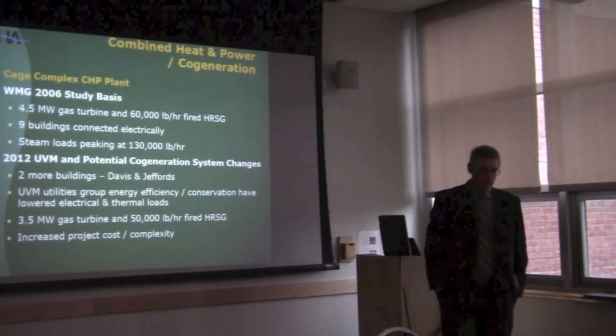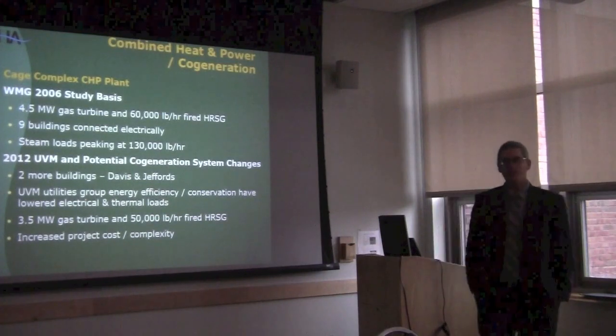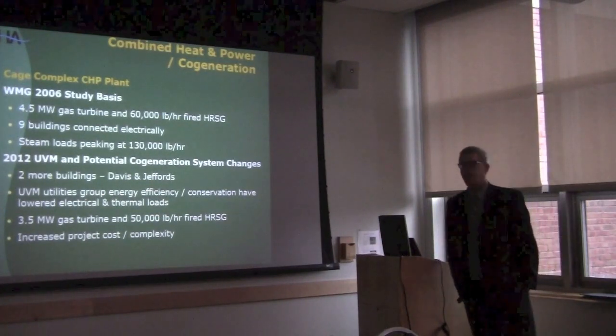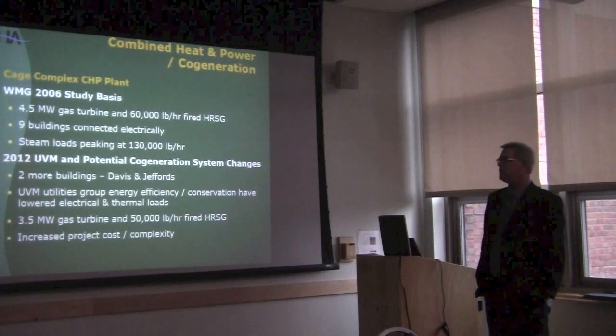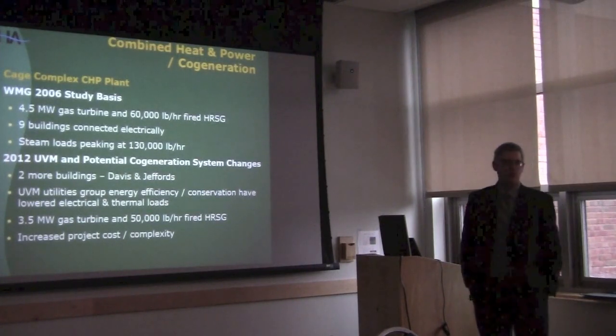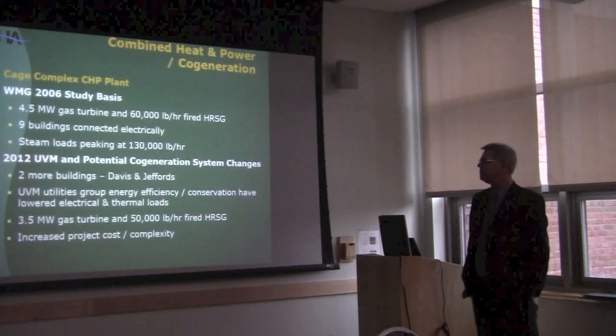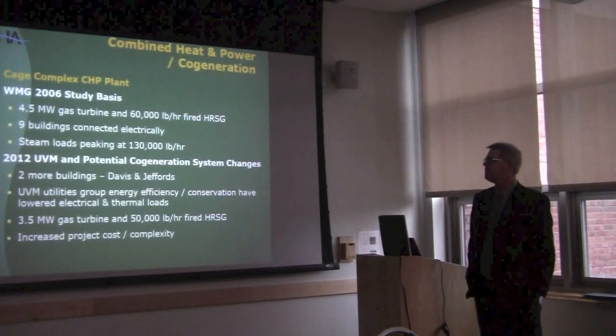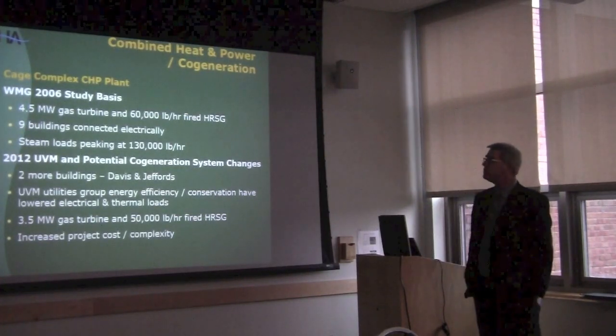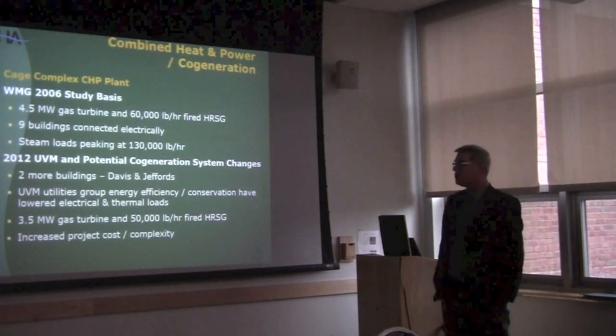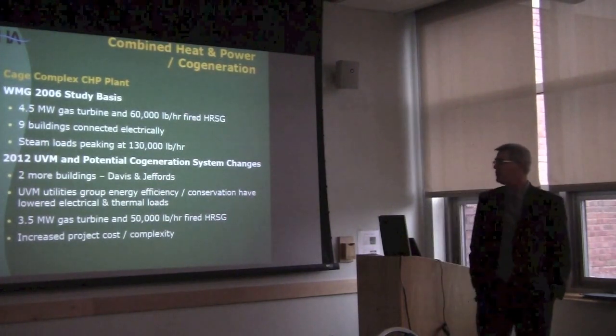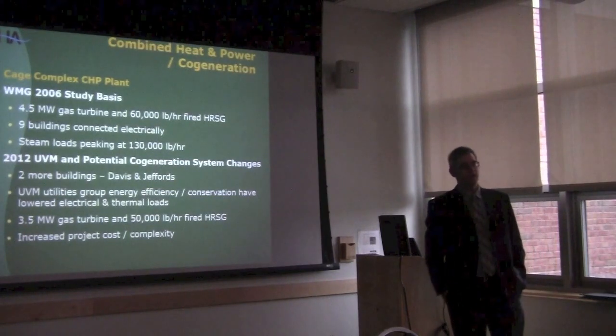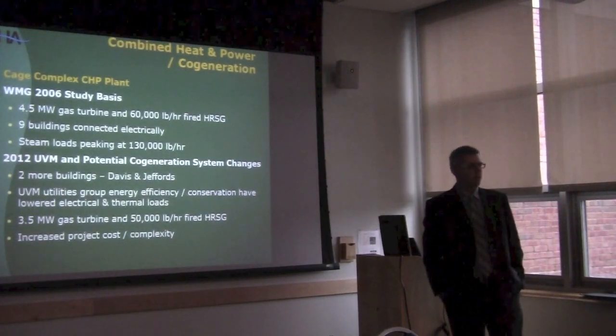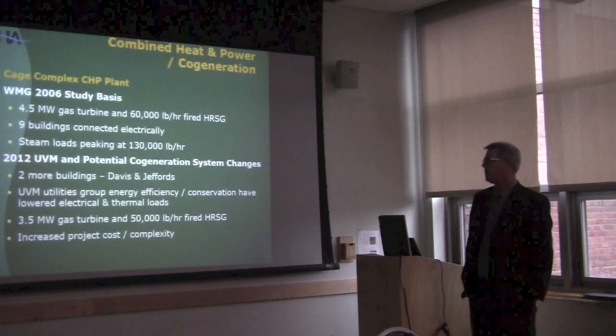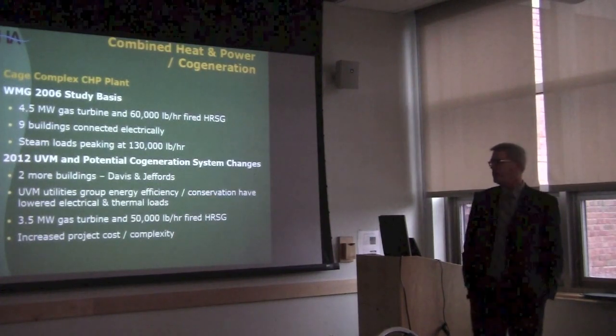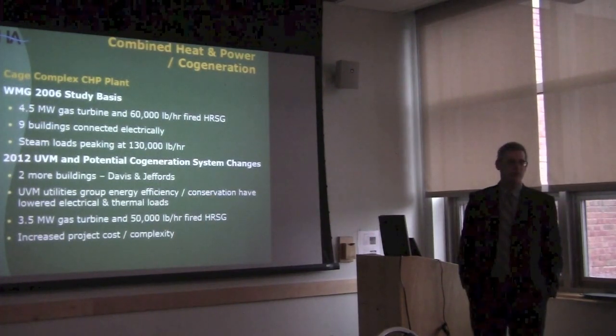At that time, steam loads out of the cage were peaking at 130,000 pounds per hour or higher. In 2012, based on information from physical facilities staff, we've added 2 more buildings. The UVM Utilities Group has done a lot of energy efficiency and conservation work, which has actually lowered electrical and thermal loads even though we've increased the number of buildings. Thus, we've ended up with a 3.5 megawatt gas turbine and a smaller fired HRSG.